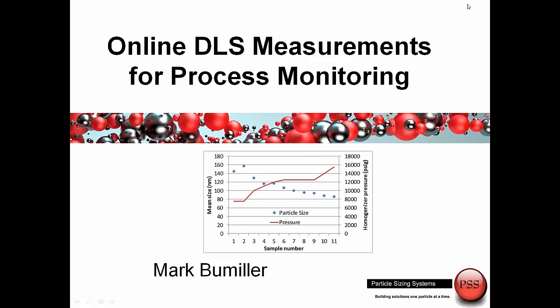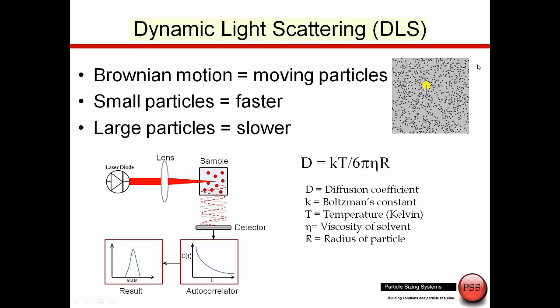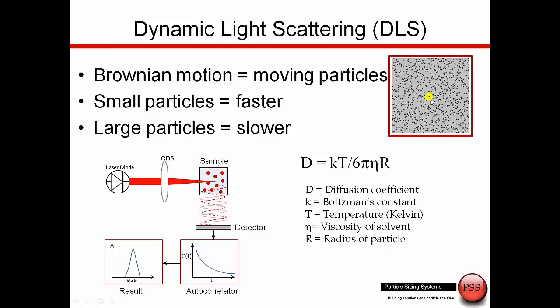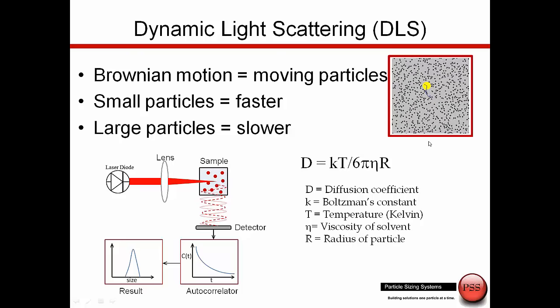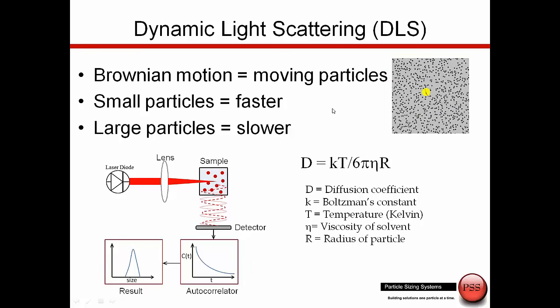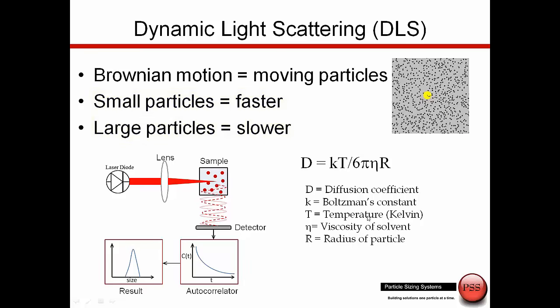The presentation today is on the topic of online DLS measurements for process monitoring. The technique we're using is dynamic light scattering. Dynamic light scattering picks up on the motion due to the Brownian motion of particles suspended in liquid. The liquid molecules impact the particle and it has a random thermal motion. That thermal motion is dependent on several things: smaller particles move faster, large particles move slower. This motion is dependent on the temperature, the viscosity, and the size of the particles.